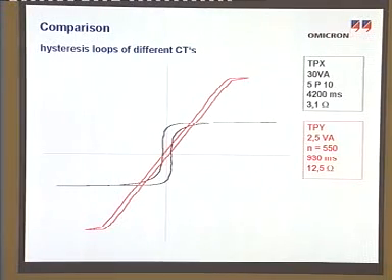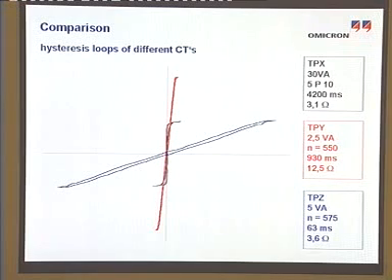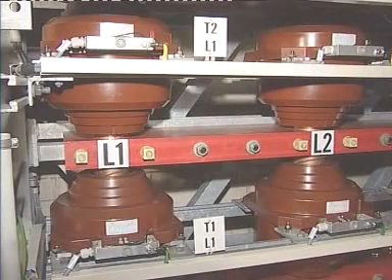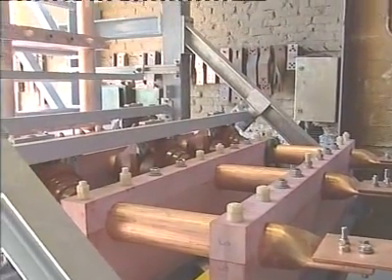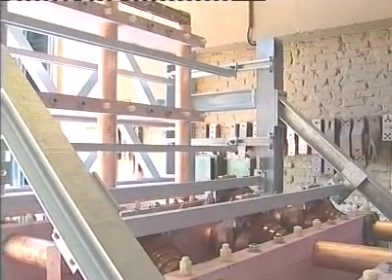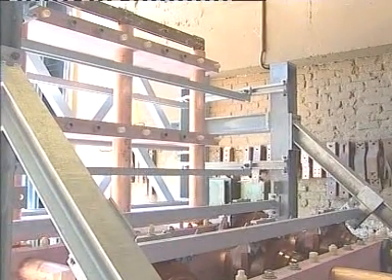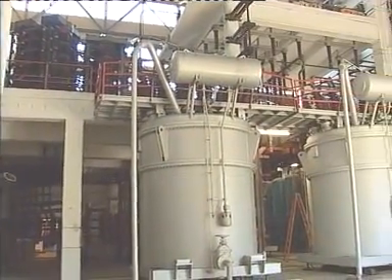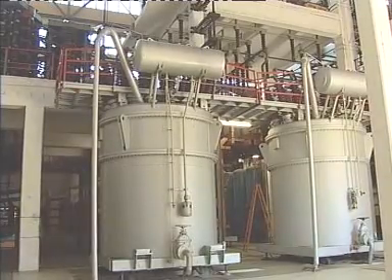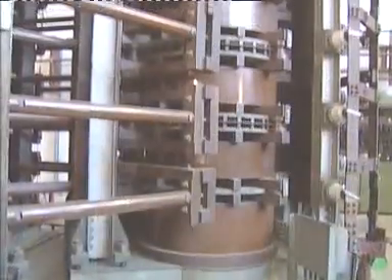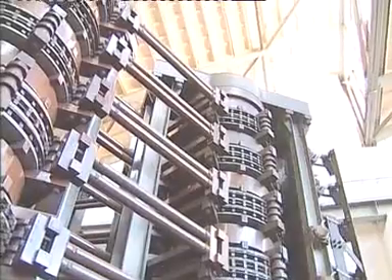Making use of an anti-remanence core or linear characteristic CTs with air gaps was discussed as a possible solution. With regard to this special application, the theoretical calculations, particularly with consideration of the thermal stress caused by the tests, were to be confirmed. For this, the designed current transformers were installed in the laboratory of the Institut Prüffeld für Elektrische Hochleistungstechnik GmbH. The necessary short-circuit currents can be adjusted automatically in amplitude, phase angle and DC offset by coils and resistances controlled remotely via PC.